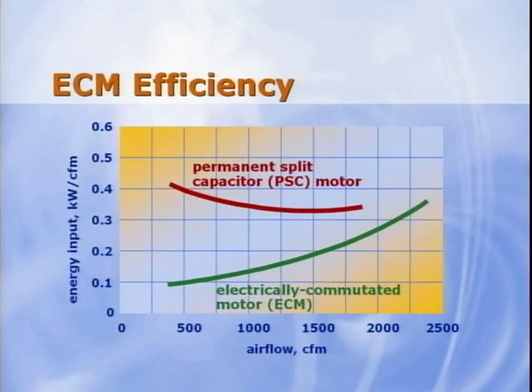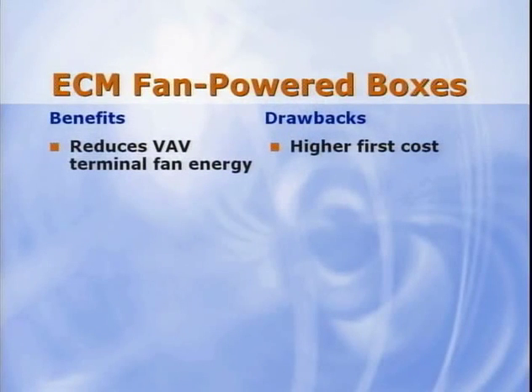This chart compares the performance of a standard AC motor with that of an ECM at various airflows for a series fan-powered box. Although the efficiency advantage is less at the upper end of the application range for the motor, the performance of the ECM really shines at the low end. This efficiency difference allows ECMs to offer substantial energy savings. Of course, they cost more than their AC counterparts, but this added cost can be offset more quickly in applications that require a relatively high number of operating hours. For this reason, ECMs are more commonly used with series fan-powered boxes, in which the terminal fan operates whenever the zone is occupied. But even if a zone may not be a good candidate for this type of motor based solely on energy savings, the decision to use an ECM may be based on other benefits.